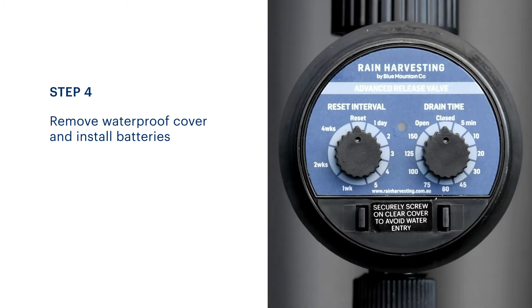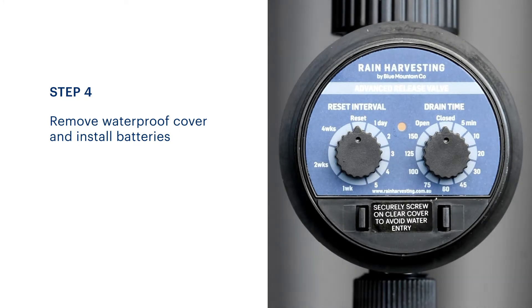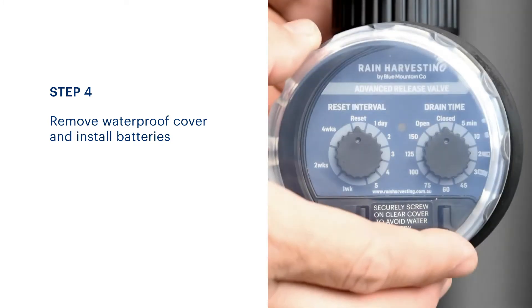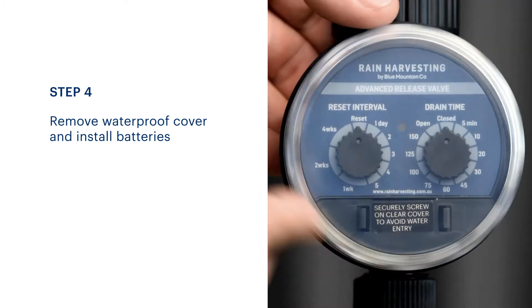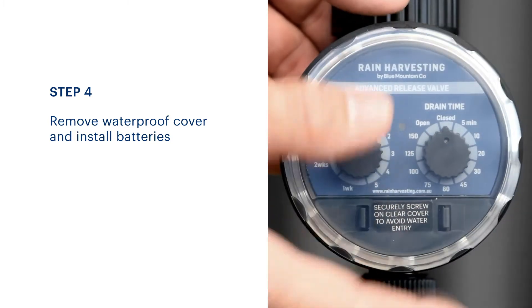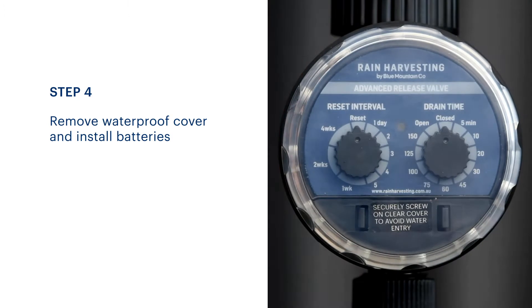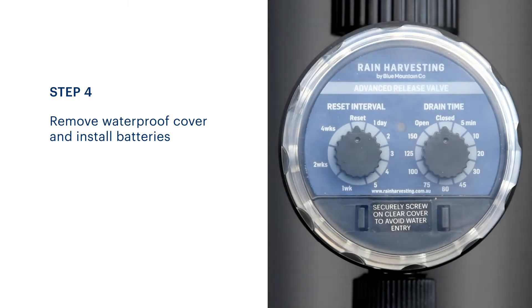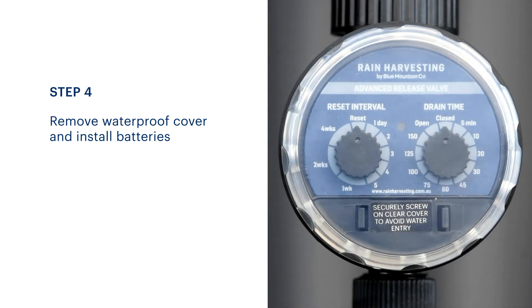To test the unit, turn the drain time knob to the open position. You should hear the sound of the motor within five seconds. Then turn the drain time knob back to the closed position, ready for setting.